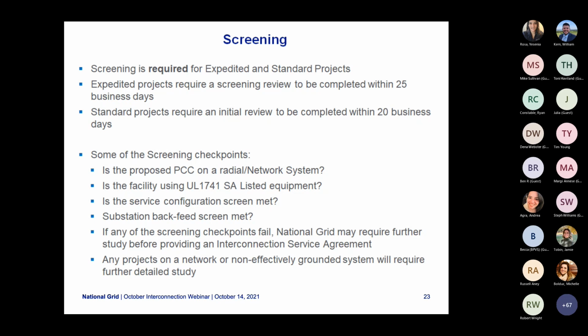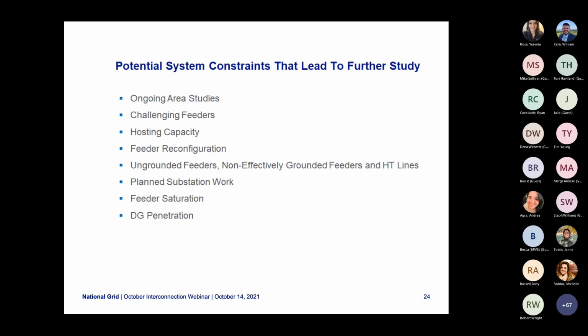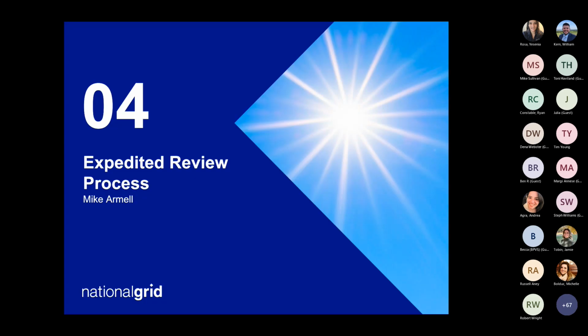Any projects on a network or non-effectively grounded system will require further detailed study. These are some of the potential system constraints that typically lead to further study, which could be challenging feeders, hosting capacity, feeder reconfigurations, ungrounded feeders, non-effectively grounded feeders and HT lines, planned substation work, feeder saturation, and DG penetration. And that's it for the pre-app, app, and screening process.